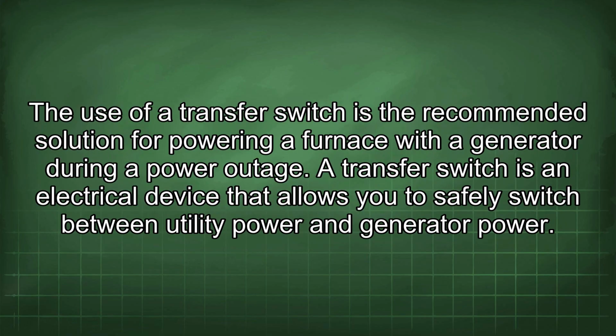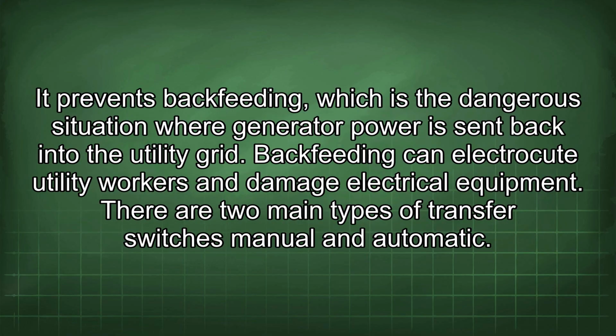The use of a transfer switch is the recommended solution for powering a furnace with a generator during a power outage. A transfer switch is an electrical device that allows you to safely switch between utility power and generator power. It prevents backfeeding, which is the dangerous situation where generator power is sent back into the utility grid. Backfeeding can electrocute utility workers and damage electrical equipment. There are two main types of transfer switches: manual and automatic.